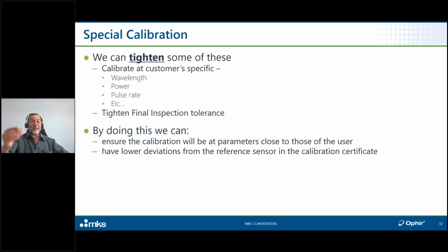We can even tighten the final inspection tolerance so that the sensors that come out will have a smaller variation. Then we could, in principle, ensure that the calibration will be at parameters as close as possible to those of the user, and therefore tighten the final deliverable accuracy in the measurements that you're going to get. I keep on saying in some cases, sometimes we can, sometimes we just can't. If it's a wavelength that's exotic and we just don't have a laser at that wavelength, unusual, but it has happened, that'll be one example.